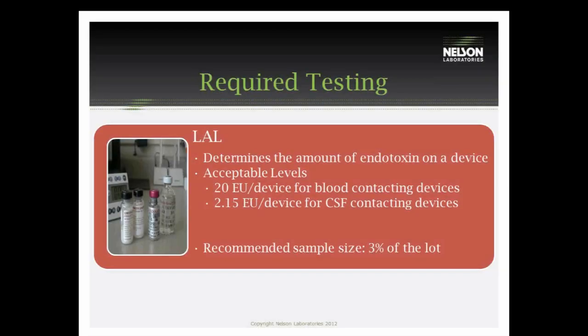Also required for testing is LAL testing. This is required for devices that have any sort of blood or cerebrospinal fluid contact. Any devices that carry a pyrogen-free claim are also subjected to this testing. There are acceptable levels established: for any device that contacts the blood, it is acceptable to have less than 20 EU per device. For any device that contacts the cerebrospinal fluid, the requirement is under 2.15 EU per device. We recommend that 3 percent of the lot be tested. There used to be a 3 percent minimum with a 10 percent maximum, but that FDA guidance document has been withdrawn, so on a conservative measure we recommend 3 percent of the lot.